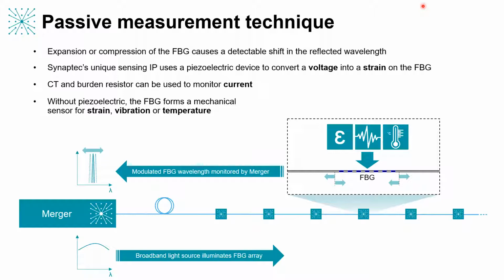If we take the piezoelectric device away, what we're left with is effectively a strain or vibration or temperature sensor. So using the same fundamental technique, whether we couple it to the piezo device or directly to, for example, the surface of a conductor or an asset, we can deploy compatible sensors to measure voltage or current, and also temperature, strain and vibration. Each of these comes back to the same central system. Each is accurately time-stamped, and all that data is available from point of measurement to publishing on, for example, a process bus in a millisecond. So it's a very, very fast acting system.